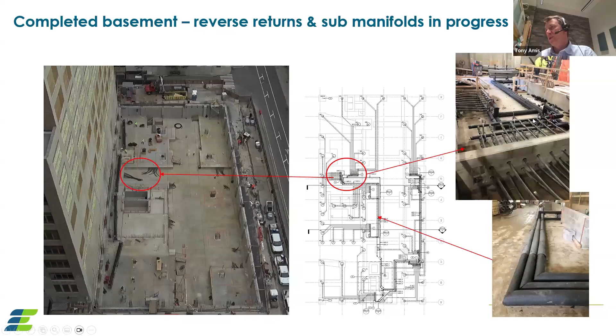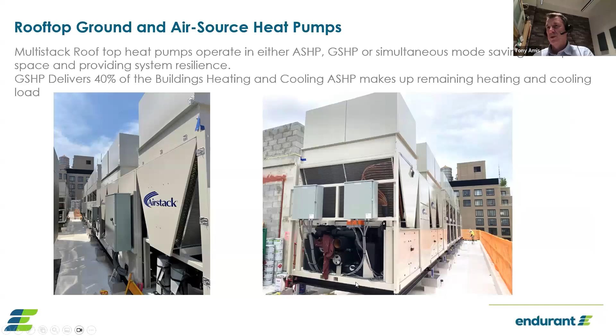And what you would see is, at the end of each of these loops to each of the piles, we would have a pressure gauge, and we would lock in a certain amount of pressure. So when the next phase of work started, we could then resume the reverse return work, knowing that the system was fully functioning. And we ended up with 63 functioning piles on this project. And then the heat pumps, and then the loops run. We've got 2 main pipes run up to the roof and the heat pumps ultimately.